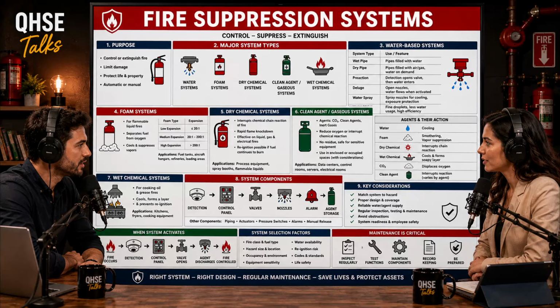But the real magic happens when water reaches 212 degrees Fahrenheit and boils. When it turns to steam. Right. Through that change of state from a liquid to a vapor, water absorbs a truly massive amount of heat energy from the surrounding fire. And furthermore, when water turns to steam, it expands roughly 1,700 times its original volume. Wait, 1,700 times? Are you serious? Yeah, it's huge. 1 gallon of liquid water turns into about 1,700 gallons of steam. That's insane. So that massive cloud of steam physically displaces the oxygen surrounding the fuel. So water primarily cools, but it also provides the secondary smothering effect.